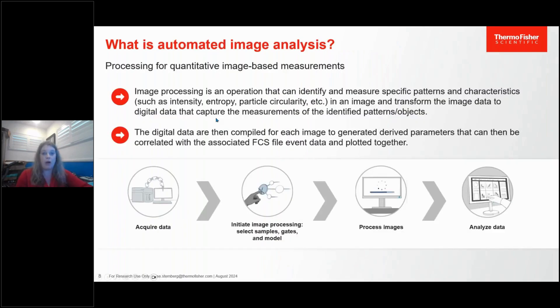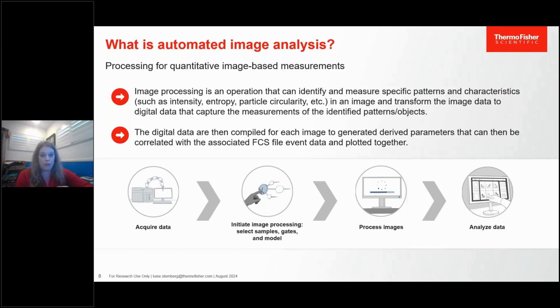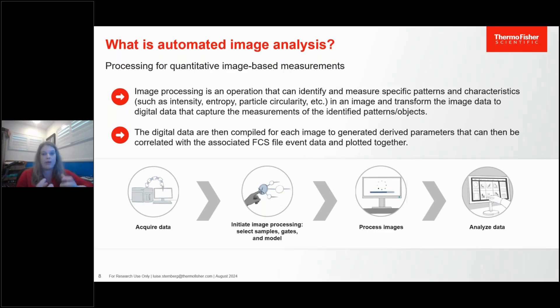Taking the image is only the first part of the operation. Once we have the image, we use software to identify and measure specific patterns and characteristics inside the cell, such as the intensity, entropy, particle circularity, et cetera. We transform this image data into actual data that you can plot on histogram plots and dot plots, just like your familiar flow cytometry data, allowing high-throughput analysis of cell populations and their morphological features. This is then combined with your flow data into an FCS file, giving you two datasets — one very high-parameter, 23-parameter dataset — from the same sample.